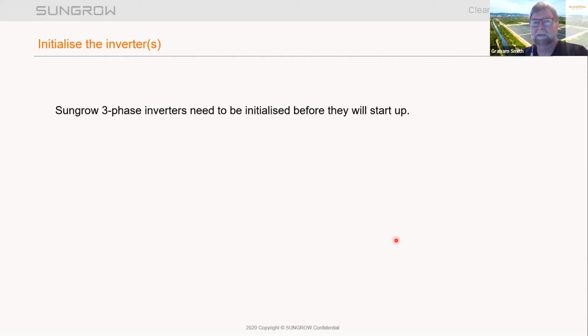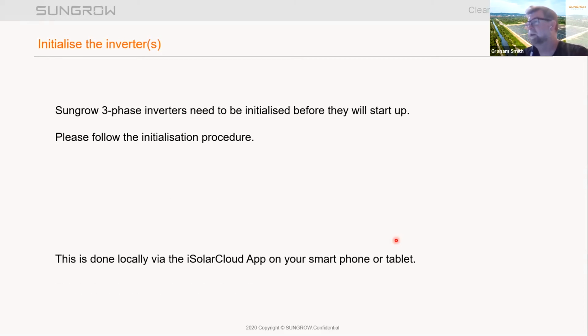They're imported, they don't have any grid connection settings loaded into them when they come into the country, so you need to actually initialize them. They will go into standby once you switch them on, and you can operate them from DC and or AC. So the following initialization procedure is how you initialize each of the inverters, and it's very easy.